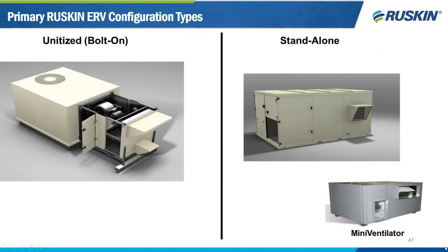The Ruskin offers three main types of ERVs here. You have your bolt-on unit. That is where we take an ERV that works right with the economizer of your rooftop, plugs right into that economizer, and you see the ERV helping with the outside air load on that rooftop.